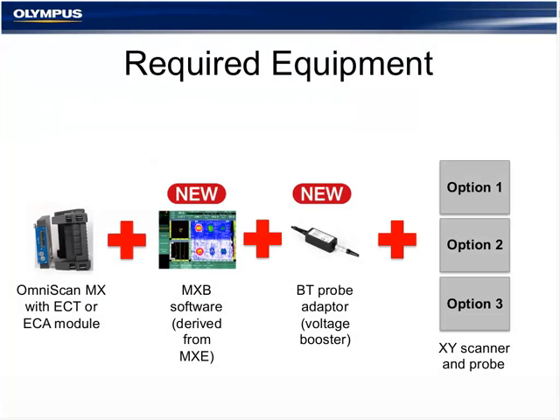The required equipment for the bond testing C-scan solution is: an OmniScan MX with the ECT or ECA module (eddy current array or eddy current four-channel module), a new MXB software derived from the MXE software (MXE = image eddy current software; MXB = bond testing), and a special adapter that is mainly a voltage adapter converting the lower-voltage eddy current signals to a high-voltage Bondmaster probe connector. The Bondmaster pitch-catch probe plugs into the adapter, which plugs into the OmniScan.